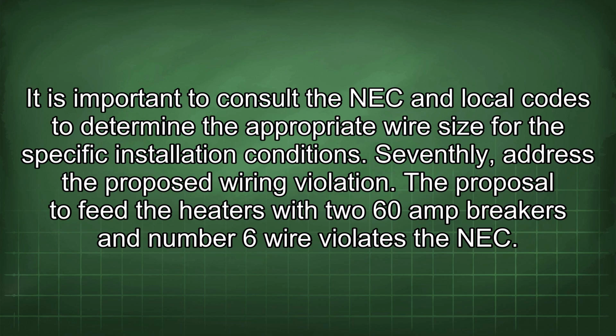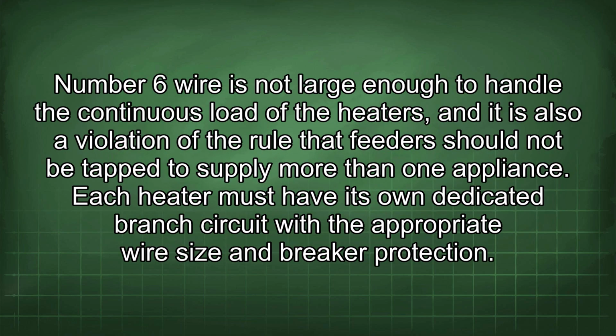Seventhly, address the proposed wiring violation. The proposal to feed the heaters with two 60 amp breakers and number 6 wire violates the NEC. Number 6 wire is not large enough to handle the continuous load of the heaters, and it is also a violation of the rule that feeders should not be tapped to supply more than one appliance. Each heater must have its own dedicated branch circuit with the appropriate wire size and breaker protection.